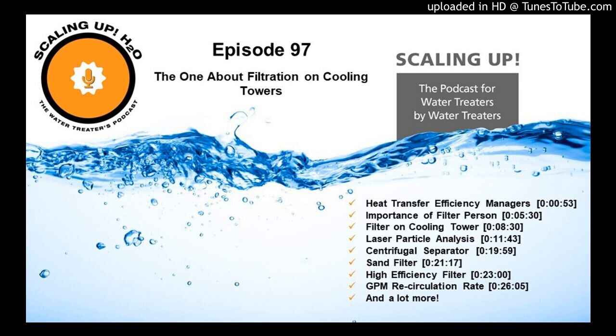The high efficiency filter is a filter design that's probably 50 years old now. The design of the high efficiency filter is they put in 0.2 millimeter sand. So that's compared to 0.55 millimeter sand. So 0.2 is much finer. If you put that 0.2 millimeter sand in a straight, normal media filter, that filter will plug up right away. You can't use that fine sand.